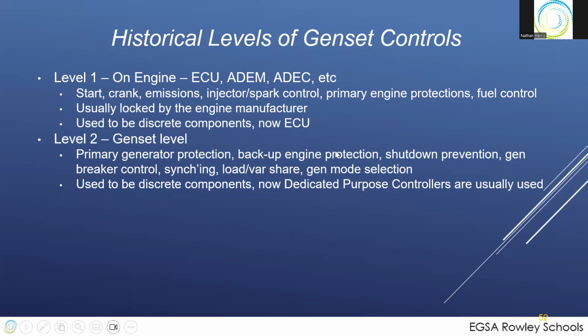We had that at the genset level. I put a generator on, I have a genset package. So this is the primary generator protection: over current, over volts, reverse power on the generator, things like that take place at this genset level. Backup engine protection: the engine protects itself, and at some temperature it will trip. In your genset control, you can often prevent a trip by saying, I'm getting hot now. I see that my outlet temperature is getting too high. I'm going to unload this machine by starting another one and take some of the load off this one so I can do shutdown prevention, prevent a shutdown, right?